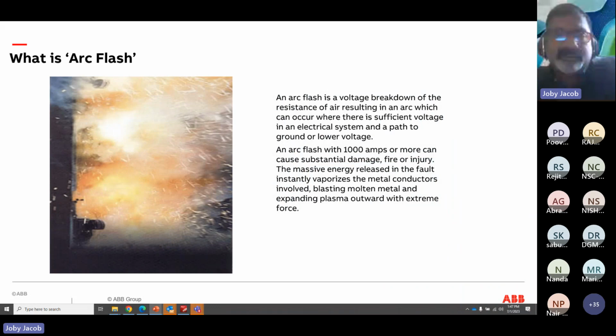So arc flash is a voltage breakdown of the resistance of air resulting in an arc, which can occur when there is sufficient voltage in the electrical system and a path to ground or to a lower voltage. So what stops the arc? Basically, when you stop the circuit itself, or when it trips or completely disconnects, or the clearance distance increases. That's how we stop the arc. Otherwise, it will continue arcing.